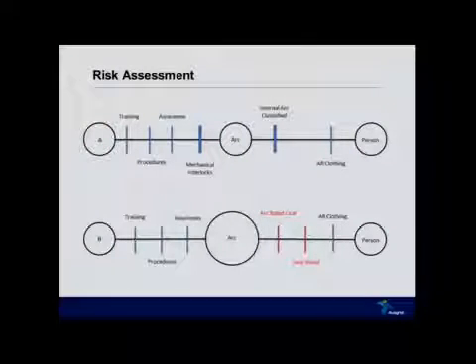I guess we haven't been looking so much at that from a switchgear design perspective, but perhaps more so in our risk assessment. As we look at our different types of switchgear, in our risk assessment, a very rough bow tie or threat barrier diagram: switchgear A has mechanical interlocks and is internal arc classified, so things to prevent the arc, but also engineering controls should it occur. Another type of switchgear without any of those engineering controls, we are looking to use higher rated PPE, so some of that switching jacket, face shield sort of stuff. But we haven't been looking at it from a switchgear design perspective, mainly from the PPE perspective that we've been looking at tests.